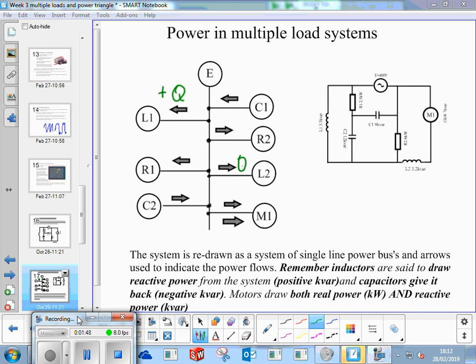An inductor is taking reactive power from the system, it's a plus Q. We've got two of them and the arrows going from the system to the inductor. We've got capacitors that give reactive power back to the system, so they are negative Q's. Resistive loads are simply powers, positive. Then a motor is going to have a portion of power and a portion of positive Q as well.